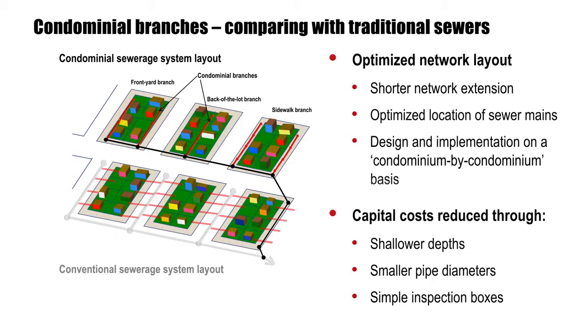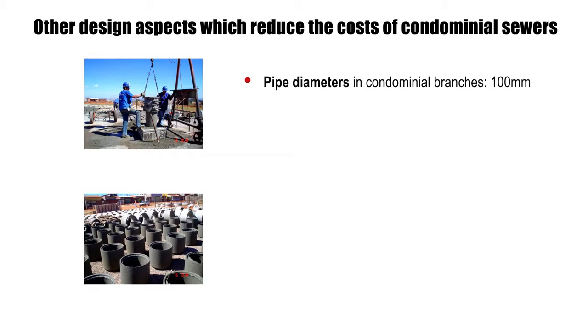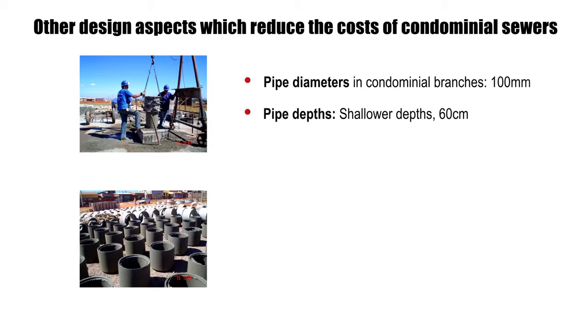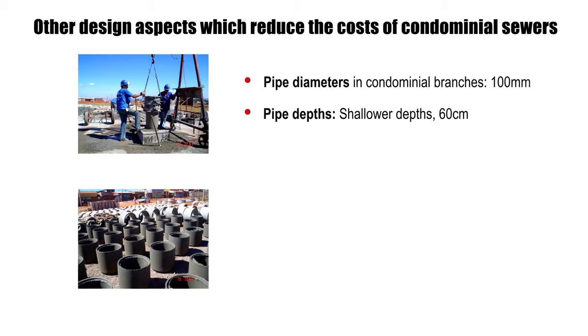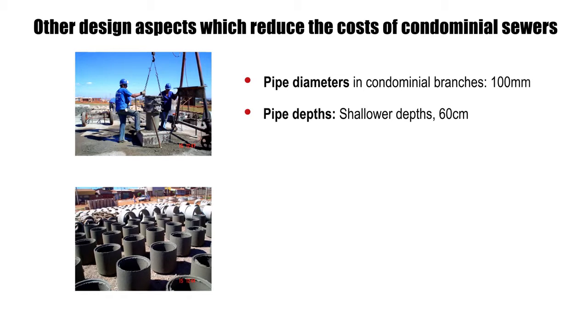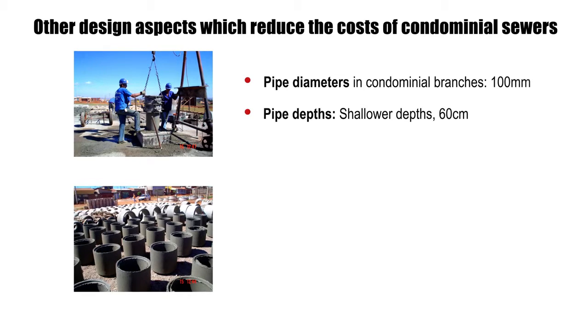Together with shallower pipe depths, smaller pipe diameters, and the use of simple inspection boxes instead of manholes, capital costs can be consequently reduced. Pipe diameters in condominial branches are generally minimized — hydraulic conditions permit a diameter of 100 mm. Shallower depths can be used when sewers are laid in front yards, backyards, or under sidewalks, avoiding traffic-bearing sites to achieve depths as little as 60 cm, reducing the amount of excavation required.